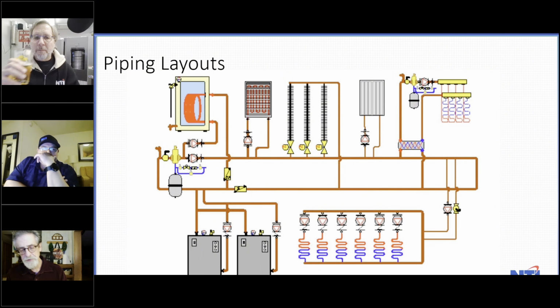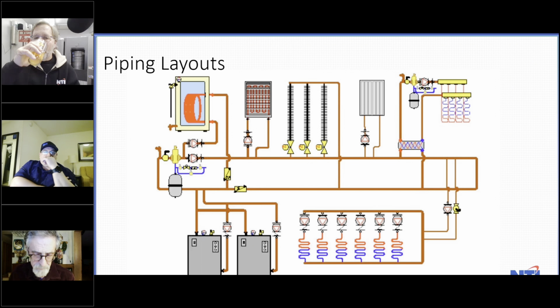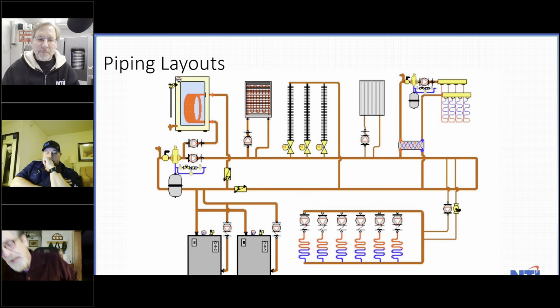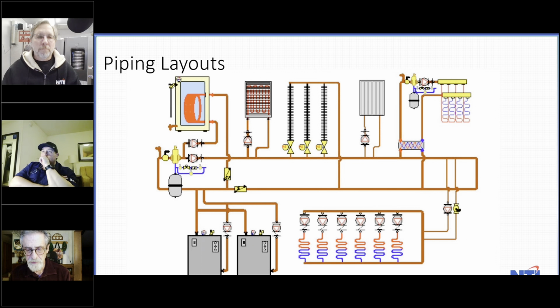The other thing too with purging a system, good point, this is only peripherally what we're talking about tonight. But if you really want to get air out of a system, you have to use a pump that's going to be better than 6 feet per second. So it's not necessarily your system pump that you're purging with. You should be using an external pump that can create 6 feet per second or greater, which is the only thing that's going to drive air out.